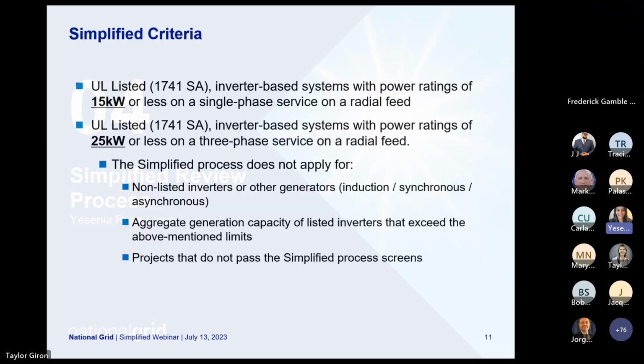I'll be going over the simplified process with you all this morning. The simplified criteria is UL listed 1741 SA, but starting later this year it will be SB inverter-based systems with power ratings of 15 kW or less on a single phase service on a radial feed, or inverter-based systems with power ratings of 25 kW or less on a three-phase service on a radial feed.